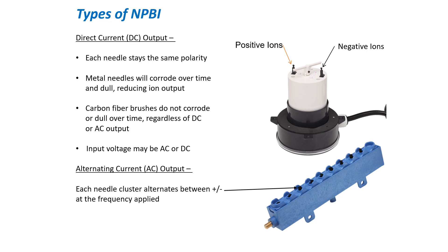With alternating current ionization systems, each individual brush cluster alternates between positive and negative based on the frequency applied — 60 Hz in the United States, 50 Hz in Europe. What sticks on one cycle will repel on the next. With our AC devices, you'll notice a wave pattern molded into the device — at the peak of the wave is where the carbon fiber brushes are located. The airflow over these brushes doesn't directly impact the brush with particles, so you don't see the brushes getting dirty from particle impaction. Because it's AC, it's static neutral, so it's not drawing particles to it the way DC technology does, which is why self-cleaning is so critical in direct current systems.